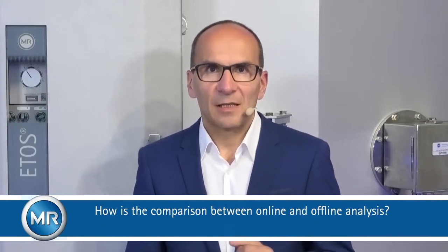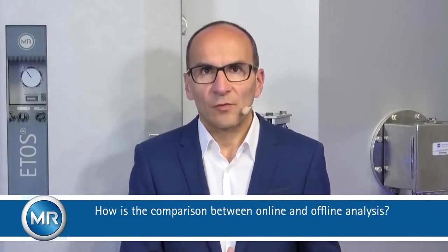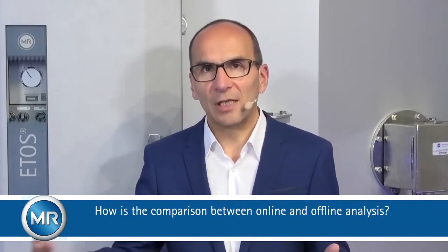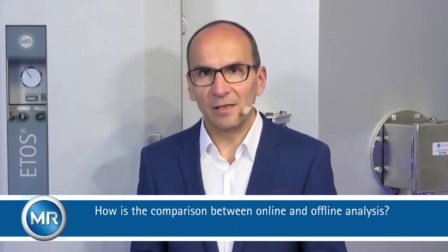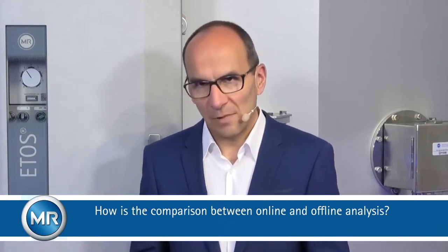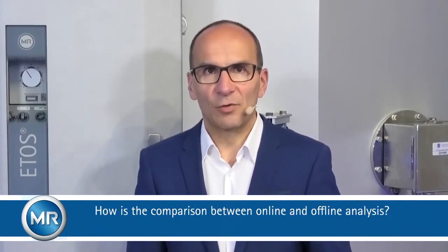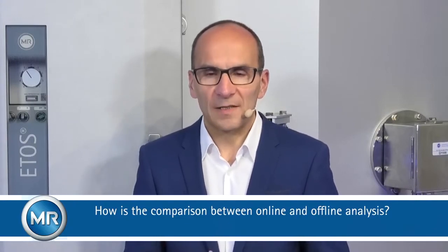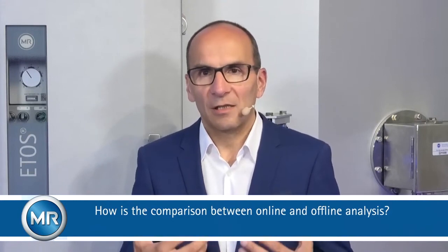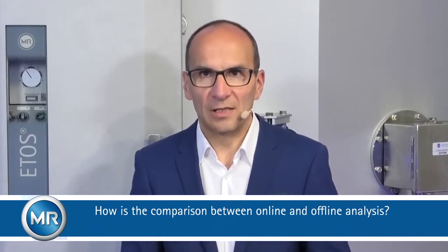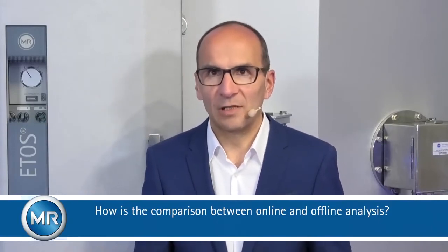This being said, with online monitoring, you get the benefits from both worlds: continuous tracking of the OLTC and the detailed data needed for root cause analysis. The second part of the question, offline analysis, that's typically a vibration diagnostic analysis, which is done once a year, twice a year, once every so often.